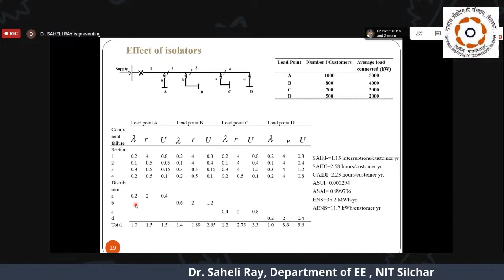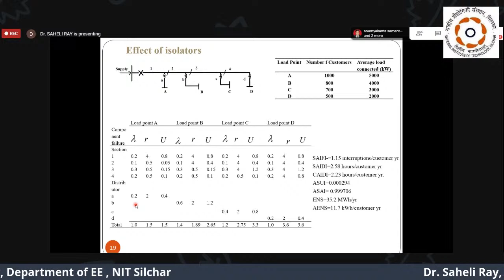But whenever a fault is occurring at distributor segment B, previously, if we go back to the previous slide, what was our concept? The fuse will operate. This will isolate segment B, and there will be no effect on load point A. Load point A will get undisturbed power supply continuously. That will not be disturbed by this fault because there is a protection device here. So we had, if we go back to the previous slide, we didn't have any contribution to the failure rate of load point A from the side of distributor B. Why? Because we considered the fuses are 100% reliable. They will be performing their intended function properly.